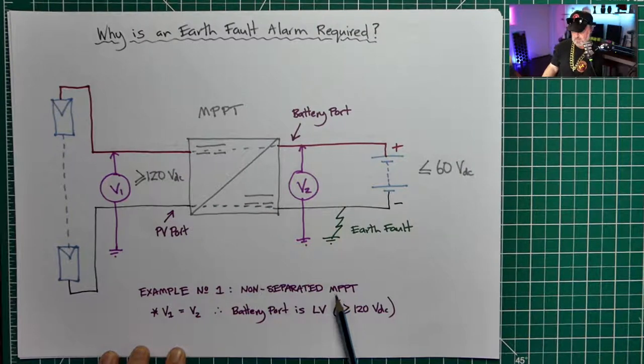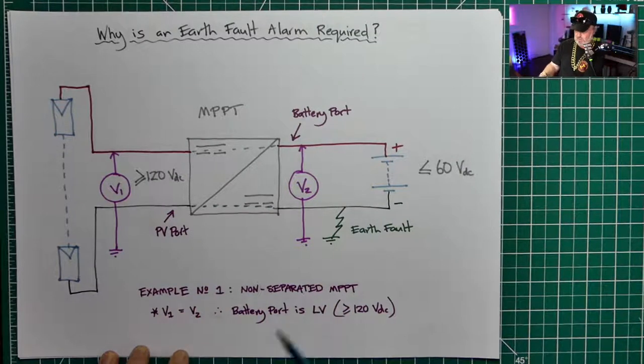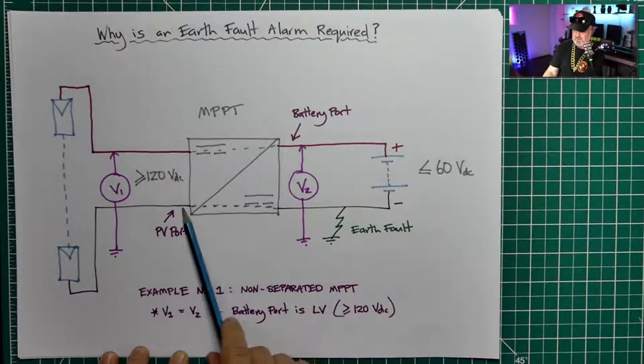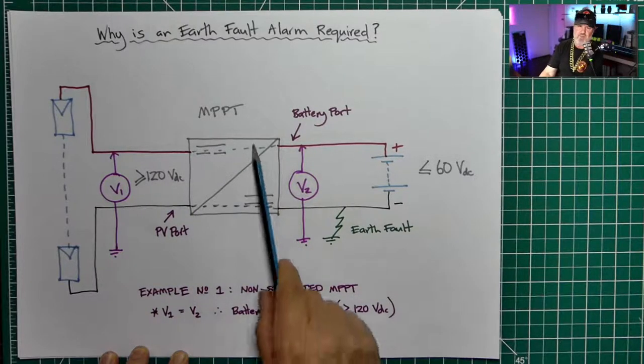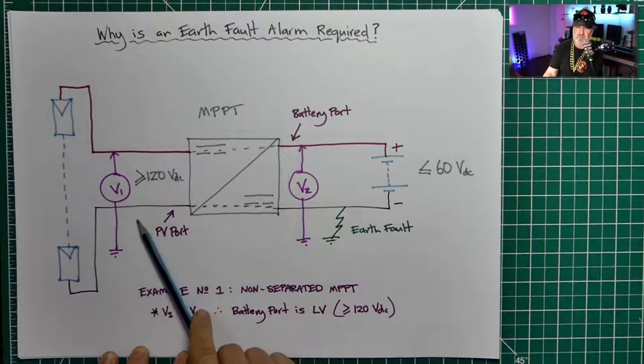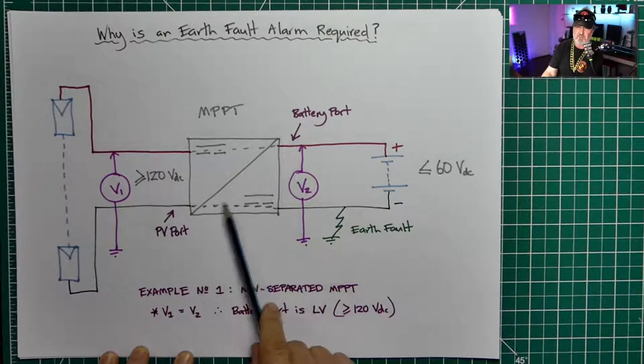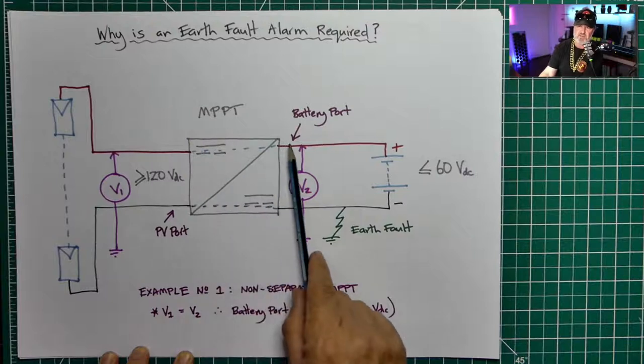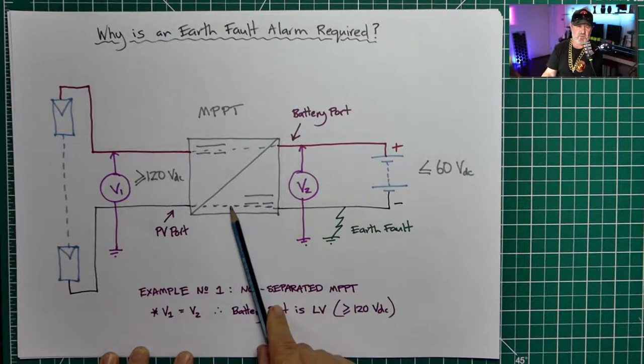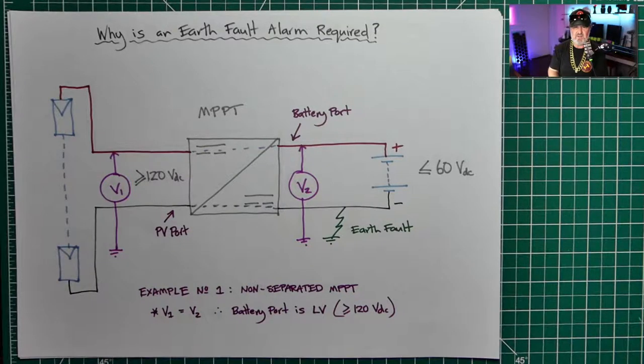A non-separated MPPT is one that has no galvanic separation. It may be that one or other of the poles are connected directly through — so the negative conductor might be passed through uninterrupted, or the positive conductor passed through uninterrupted. When it's operating, it's switching electronics doing the conversion — it's not actually providing galvanic isolation.